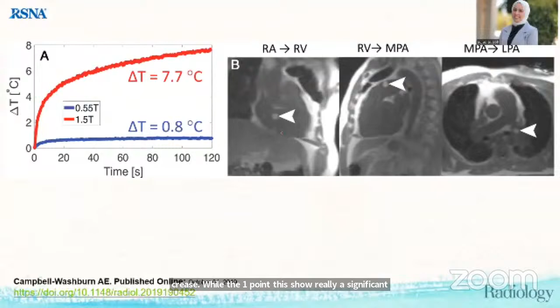So, challenges and considerations when we talk about low field: lower SNR and resolution. Low-field MRI inherently has a lower signal-to-noise ratio and reduced resolution compared to high-field systems. This is due to the weaker magnetic field strength, which produces a weaker signal from the tissue being imaged. Lower SNR can result in images that are less clear, making it more challenging to find details, which is critical for accurate diagnosis. But technology innovations, machine learning and mathematical algorithms help overcome this problem and improve the image quality, reduce the noise, and increase spatial resolution. These techniques include deep learning reconstruction, sequence optimization, and high relaxivity contrast agents.